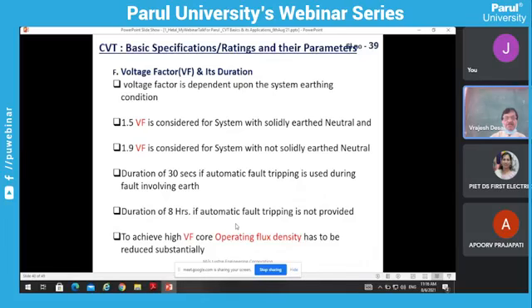So this is how the voltage factor is specified for the CVT, and we have to actually test the CVT with this kind of voltage, 1.5 to 1.9 times. The duration is also limited here. A 30-second duration you can allow when you have automatic fault tripping by the devices. If that is not there, then you have to design the CVT magnetic core such that it can withstand for 8 hours. It means that 16,000 gauss, that is 1.6 Tesla, is the operating flux density, but we cannot design with that. We have to reduce it to half, about 0.8 Tesla, as the working flux density, so that it can meet the voltage factors like 1.5 and 1.9.